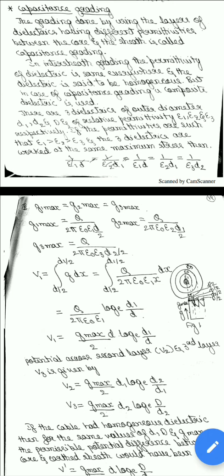Today we shall discuss capacitance grading. Why do we need capacitance grading? To make the uniform distribution of stress in the insulation of the cable. The grading done by using layers of dielectric having different permittivity between the core and the sheath is called capacitance grading. In this we are using three dielectrics of outer diameter d1, d2 and capital D, of relative permittivity epsilon 1, epsilon 2, epsilon 3. The three dielectrics work at the same maximum stress.